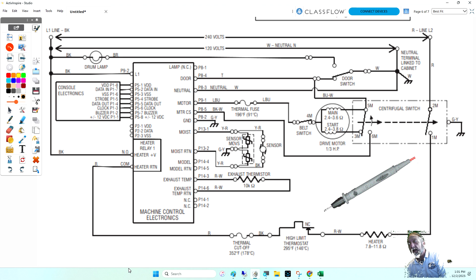And to neutral, T to W, right? T to W, or let's be more specific, the actual plug and the wire on that plug. Hold on, say that again. Well, we said P9-1 and P9-2 because P9 is the plug and 1 and 2 is the first and second wire on that plug. So where on this board would I jump the door switch? You said TW - TW is what? The color of the wires, tan and white.